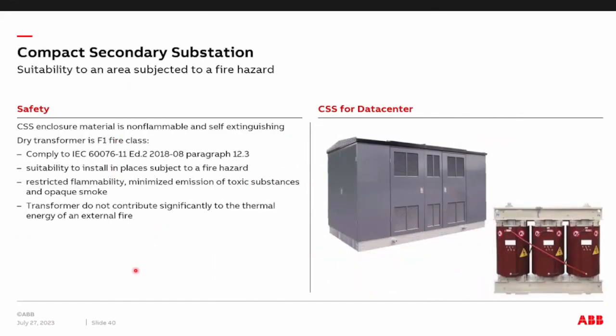So since our transformer, for example, if we are actually providing a dry type transformer, our dry type transformer is actually an F1 fire class. It complies to IEC 60076-11, which actually does not require any external fire protection system.